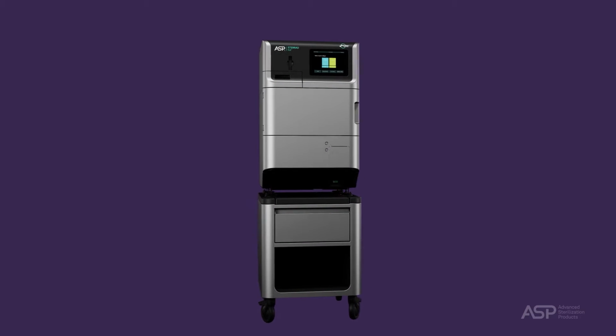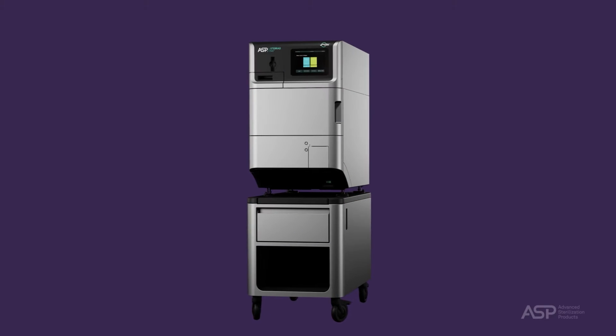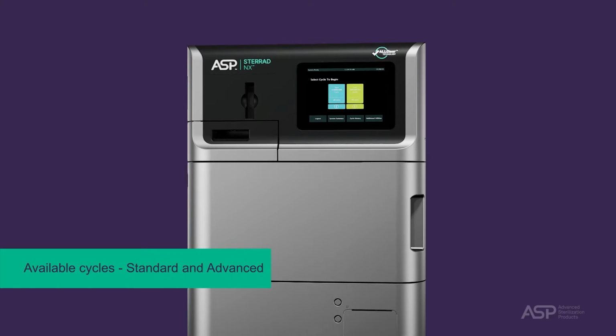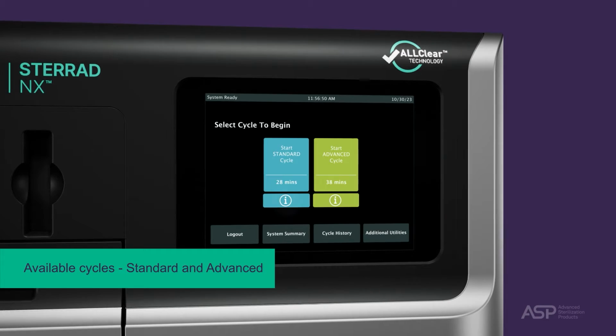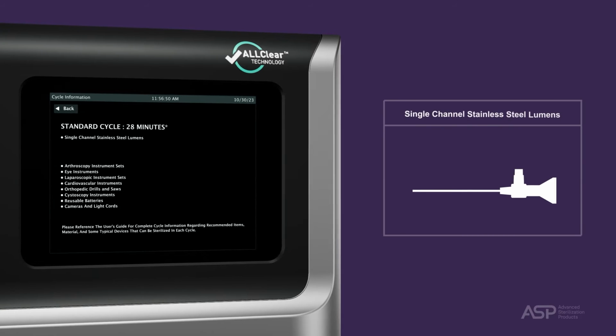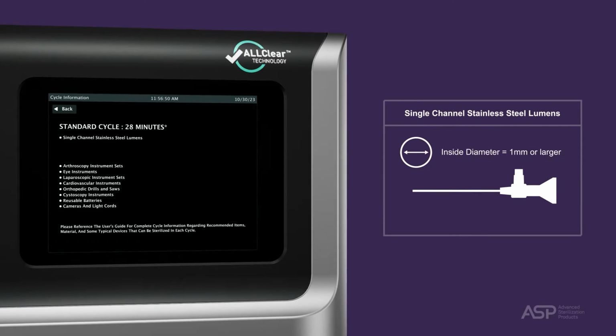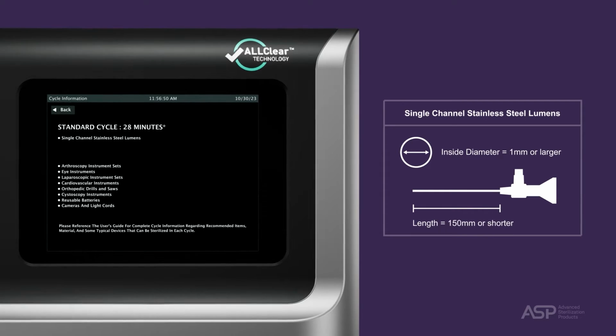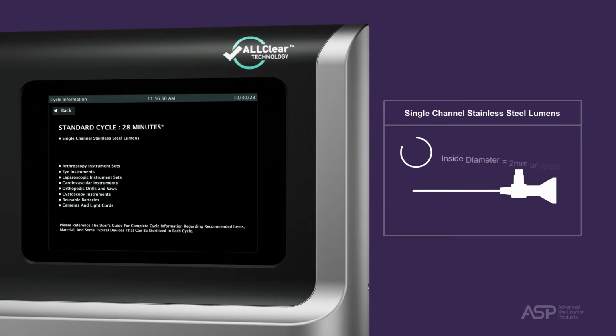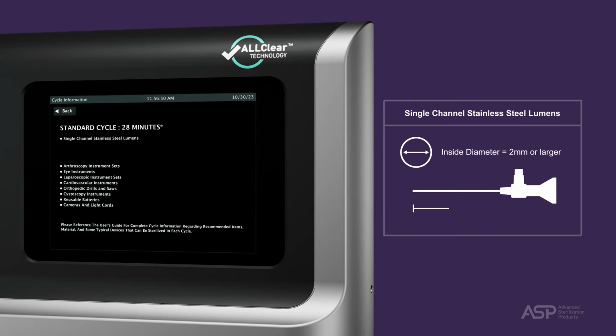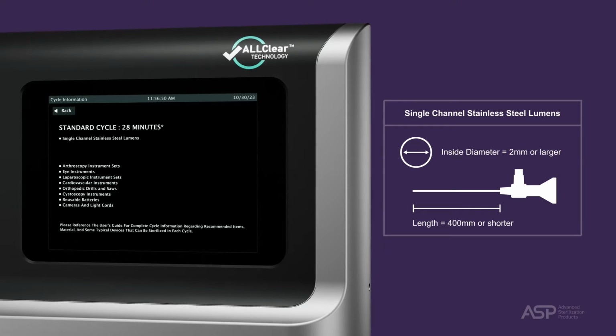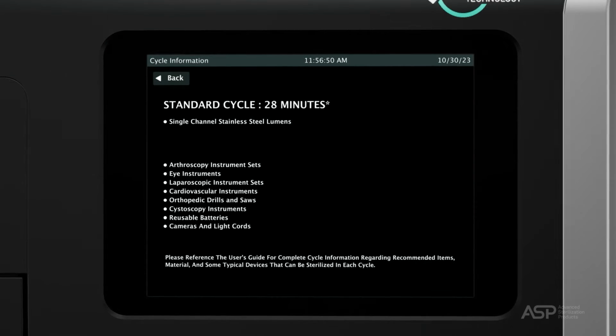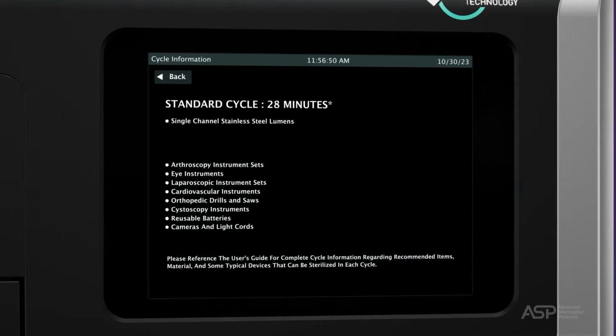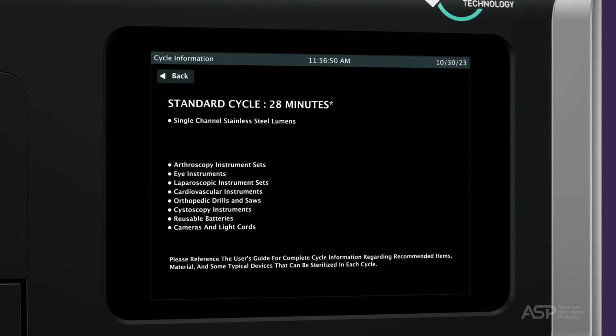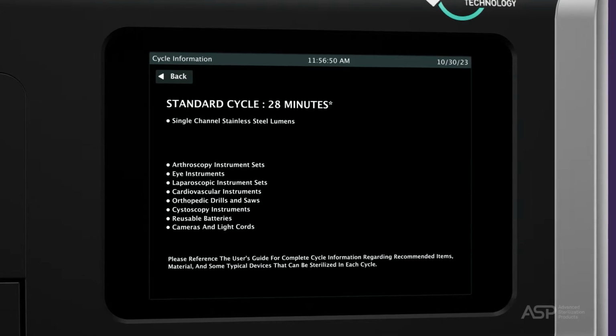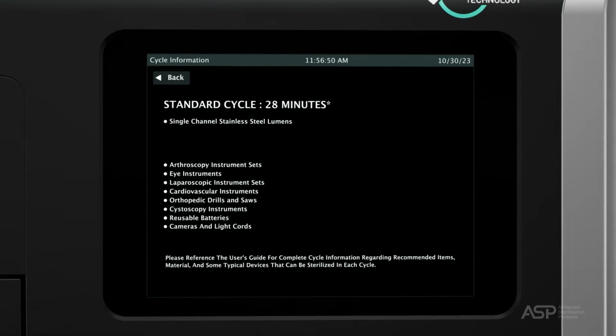Let's review the cycles and what can be reprocessed in the STERRAD NX sterilizer with ALLClear technology. The available cycles are standard and advanced. The standard cycle is 28 minutes and should be selected for single-channel stainless steel lumens with an inside diameter of 1 mm or larger and a length of 150 mm or shorter, and single-channel stainless steel lumens with an inside diameter of 2 mm or larger and a length of 400 mm or shorter. Typical devices will include arthroscopy instrument sets, eye instruments, laparoscopic instrument sets, cardiovascular instruments, orthopedic drills and saws, cystoscopy instruments, reusable batteries, cameras, and light cords.